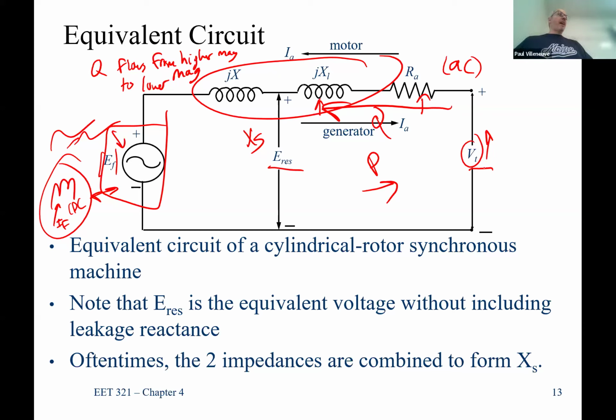More often than not, though, the magnitude of the terminal voltage is going to be lower because most systems in the real world are operated in what's called an overexcited condition. The grid needs more reactive power because we tend to operate more at a lagging power factor than a leading power factor.